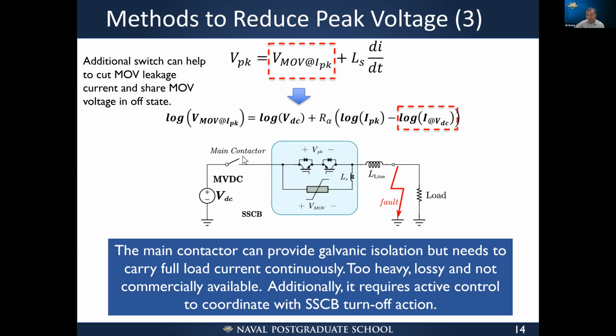However, this is too heavy, right? Because this main contact needs to carry 1200 amps continuously, so you need a big chunk of copper to do that, and it could be lossy. And also, most important, it is not commercially available. And this component needs to be available by 2023 to support NASA's flight test. And additionally, it requires active control to coordinate with the solid-state circuit breaker turn off actions, right?